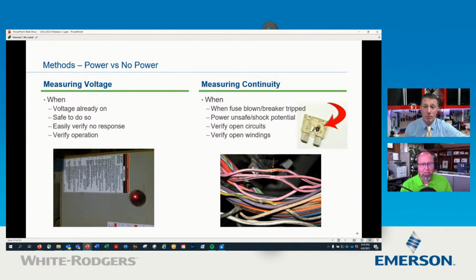So you're no longer only checking resistance. You used to be able to check resistance on them very easily. Yeah. And then continuity, measuring that when you got something tripped. And in this picture here, I actually show there's a little wire that's skinned there. Again, your visual and actually checking wires, and a lot of times when I'm out on a piece of equipment that had a blown fuse, I was using my hand to gently move wires away. Half the time there'd be a little black mark on the sheet metal where that arc was, and then you could turn the wire and there it is. That's where the insulation rubbed off.